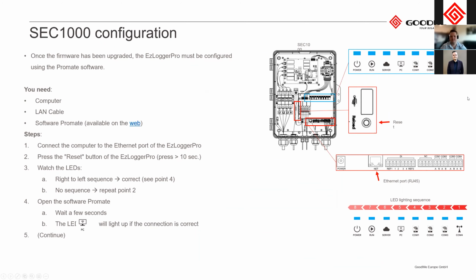So for the EzLoggerPro, on the LAN connection, we have two different types of statuses. We have DHCP. DHCP is when you connect it to a router and it automatically gets an IP address from that router. But in order for us to directly connect to it with a computer, we need to make sure that this device is set to static. As default, they will all come out with DHCP. So that's the dynamic mode.